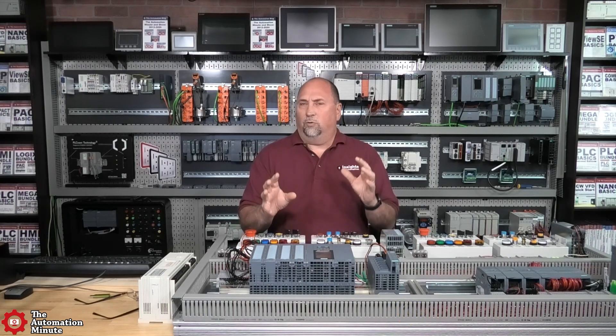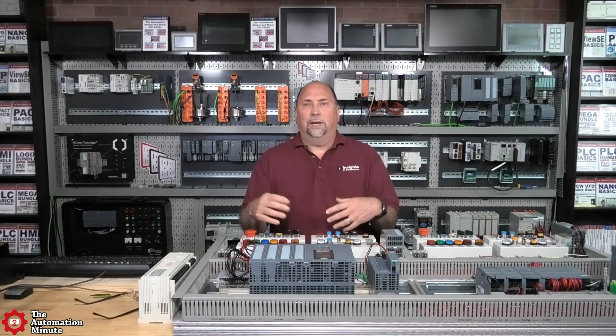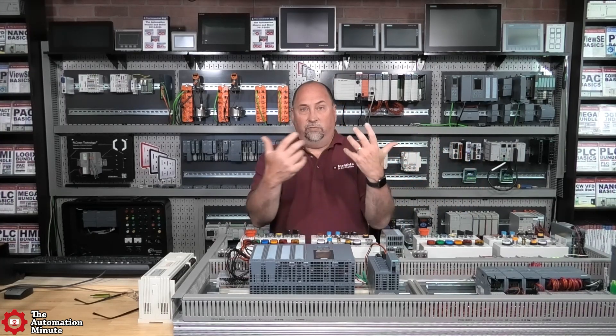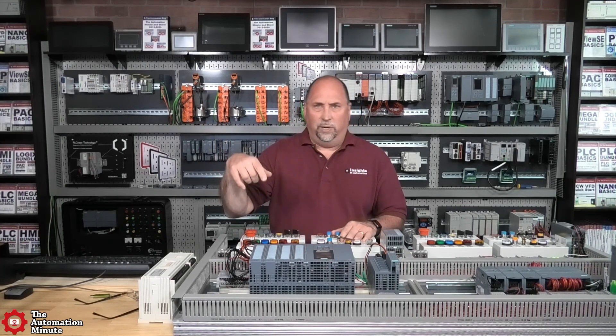But if you did that correctly and you're still not seeing historical data, it could be a couple of things. One thing I used to love showing people is the difference between the onscreen buffer and the data log. I'd set the data log up to log every five seconds, set the screen to buffer data every one second, and give the screen and the data log very large buffers. Then I'd let it run for a minute.